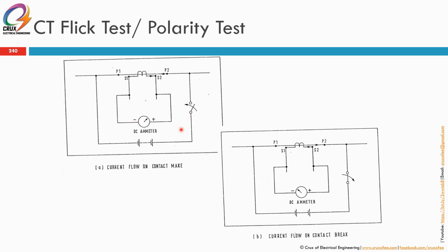So when you switch on and off the switch, you will know the direction of the CT, whether it is correct or not. By right, for example, if you are testing this for red, yellow, blue and neutral phase of an LV busbar CTs, you must make sure that you connect the batteries and the meter in the same connection for all these 4 phases. When you flick on and off the switch, the direction of the CT, the meter must be pointing in the same direction.